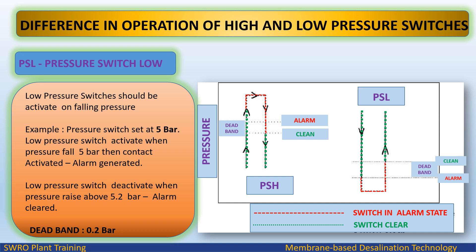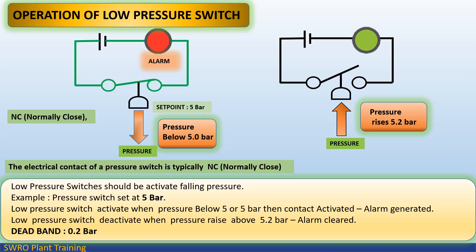Operation of a low pressure switch. Low pressure switches should activate on falling pressure. Example: pressure switch set at 5 bar. The low pressure switch activates when pressure falls to 5 bar — contact is activated and alarm is generated. The low pressure switch deactivates when pressure rises above 5.2 bar and the alarm is cleared. Dead band: 0.2 bar. The electrical contact of a low pressure switch is typically NC (normally closed).